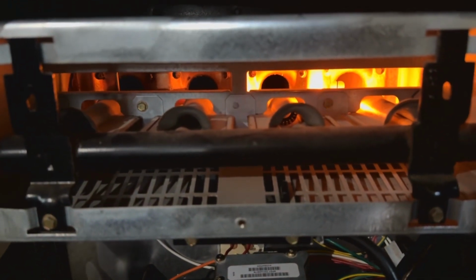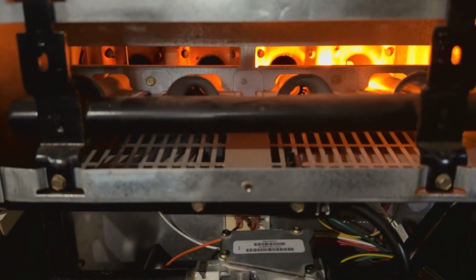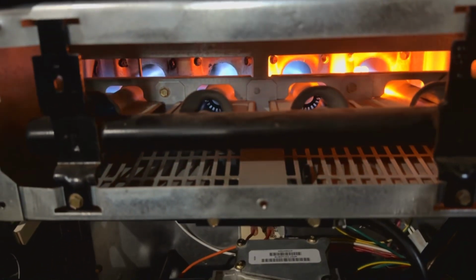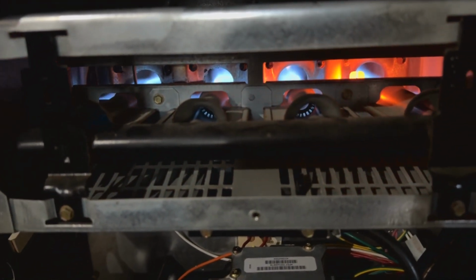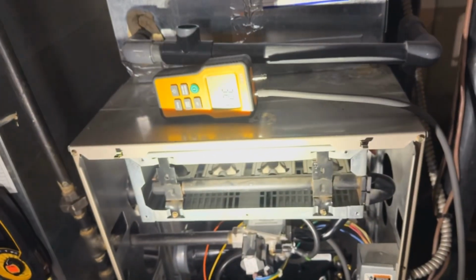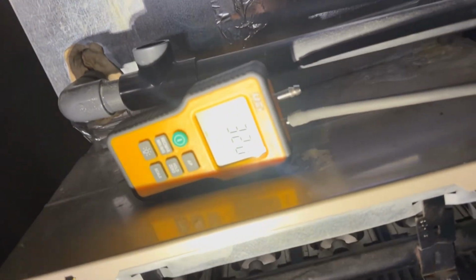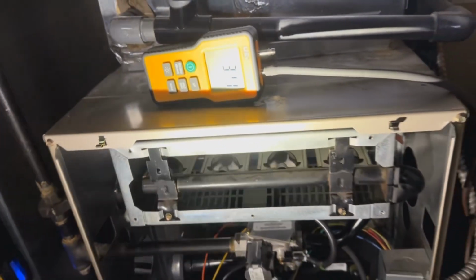So there's the igniter, followed by the blue flame. At the lower end of the scale, you want me to bump that up to 3.5? Alright, so as you can all see, I'm at 3.2 inches water column. I've usually kept it around 3.5, so I'll make a little adjustment for you.